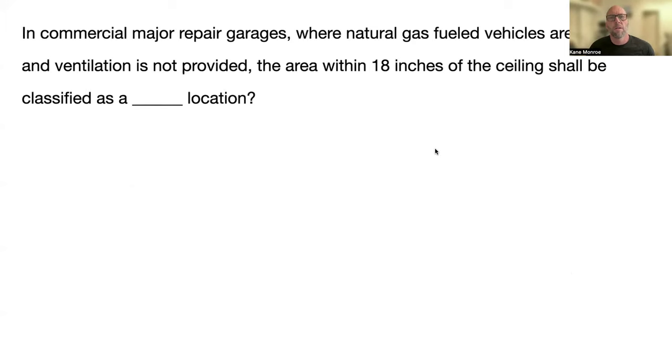In a commercial major repair garages where natural gas fueled vehicles are repaired and ventilation is not provided, the area within 18 inches of the ceiling shall be classified as a blank location. And that's a Class 1, Division 2 area, 511.3D and table 511.3D.